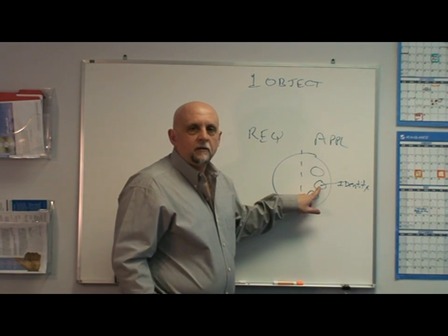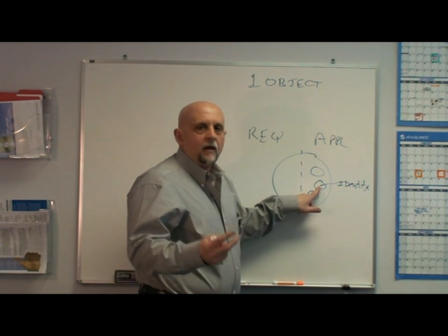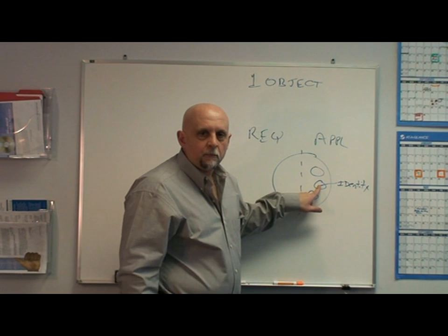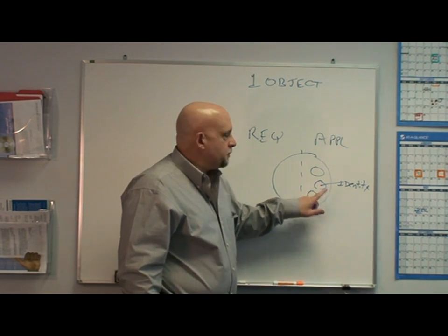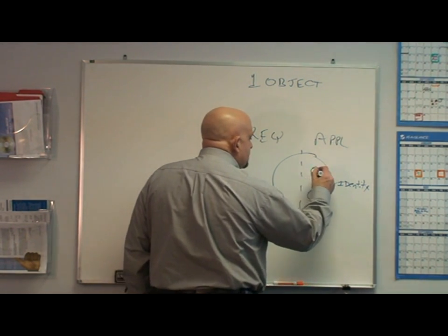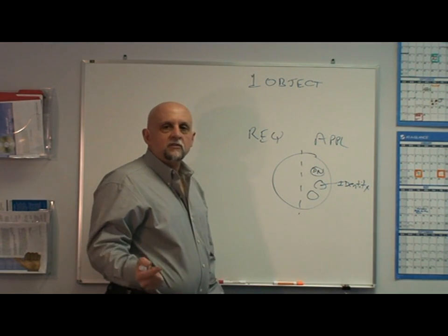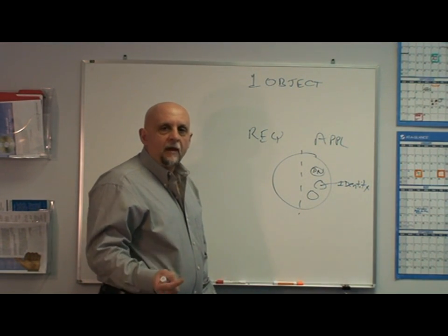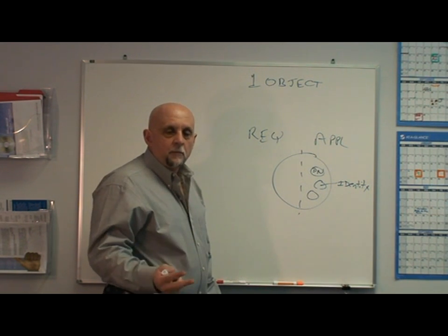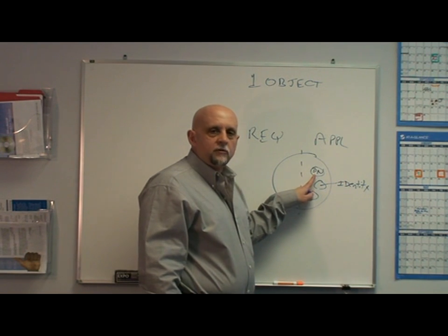The identity object contains things like manufacturer data, vendor ID, serial number, model number, descriptive string name — all the things that describe the device. There's also a DeviceNet object. The DeviceNet object has things like the DeviceNet MAC ID, which is the address on the bus, the baud rate being used, and everything concerned with the DeviceNet configuration.